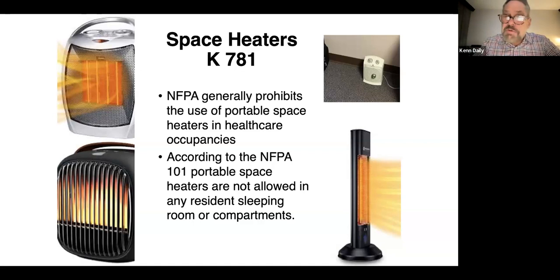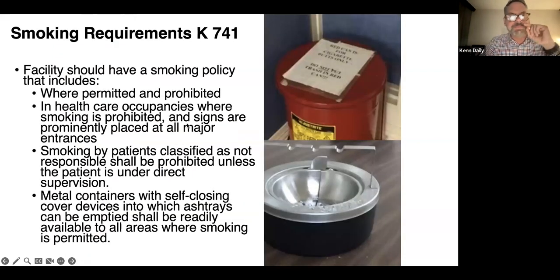And even if you were permitted, even if you got a statement from the manufacturer saying, okay, the heating element only goes to 192 degrees, yay. Where do you guys see most of these? Under a desk. Well, let's pull up the manufacturer specifications. What does it say? Keep 3 to 5 feet from all furniture and drapes. Well, there again, there's no path to compliance because you just violated the manufacturer's specs. So again, no path to compliance for these devices. There's no purpose for these devices in facilities. Not that it doesn't get cold, I suppose, but it's not right.